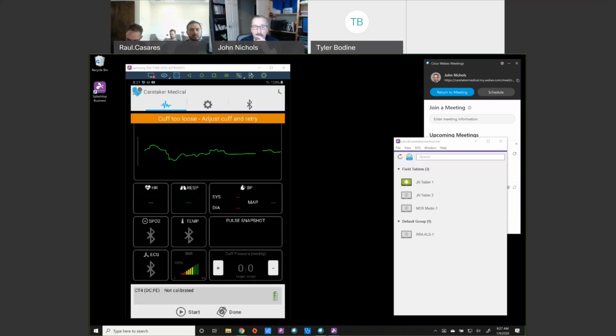Okay. Now again, Raul, let's get you to keep your hand still for a second, and let's see if we can see a pulse pressure wave off your finger. Okay, so this is an important note. Do you see what's going on the screen, Raul? Yes, sir. Okay, so what we're seeing is a pulse pressure wave, and we're seeing a very clear dicrotic notch on that pulse pressure wave. So what this is telling me is you've got your cuff on correctly, and we're already starting to see a good pulse pressure wave. So go ahead, hit start one more time.